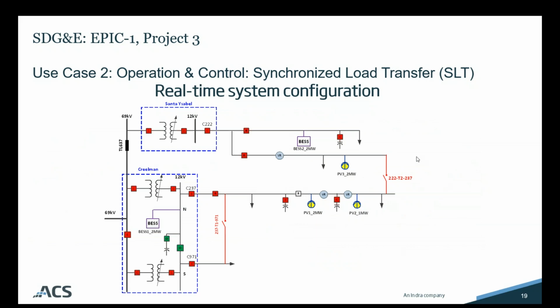So what we want to show here, we're showing the same example. Coming off the Creelman feeder, we have a load coming down line, and what we wanted to model was a loss of a large load. How would this react? As you can imagine, if you lose a large load, and maybe we're in the middle of the day, noon, 1 o'clock, we're going to have a maximum amount of PV injection from these downline PV arrays.